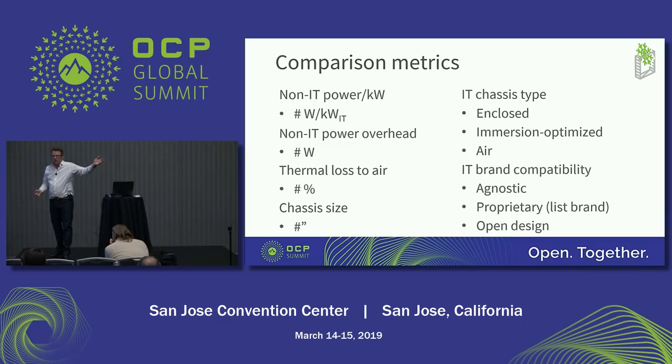So for example, we've done a large deployment in Holland, and that room contains zero ventilation, which is not according to our recommendation. But the operator wanted it that way because he was curious. What we've noticed is that throughout the year, we had a heat wave last summer, a long one. And even during that heat wave, the temperature inside the room remained relatively equal to the outside temperature. It didn't really rise, even though there was zero ventilation. Why is that? Because our systems are completely thermally insulated, with double-hulled thermal insulation in between, and even the lid is doubled, right? But until you open it.